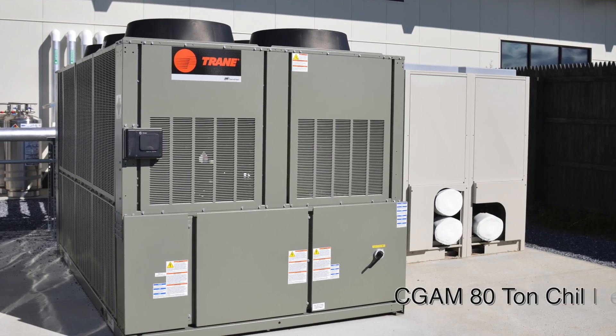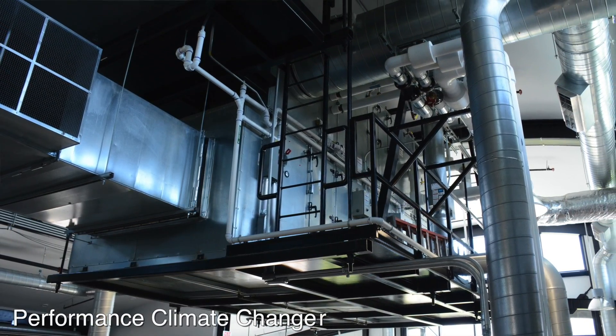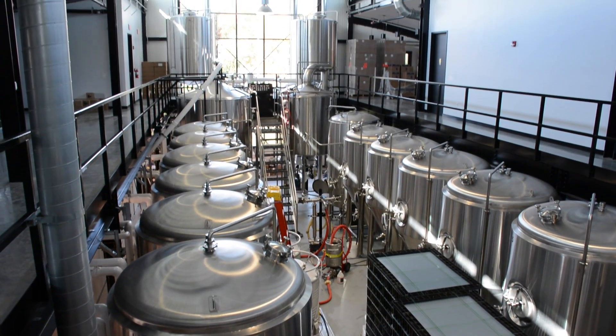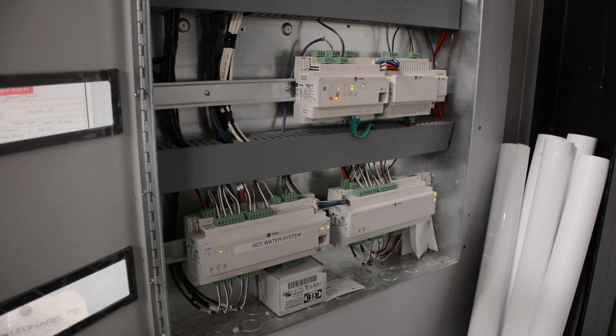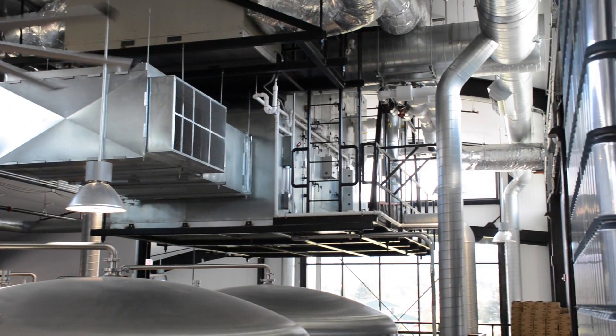For the chilled water system on this project, we chose a Trane C-GAM 80-ton chiller, and it has onboard pumps with VFDs. The main reason they chose to do it that way is that it limited the footprint inside the building and allowed the brewery to have more space for their own systems, limiting the mechanical space required. It also has factory-mounted controls, which limited the amount of conduit and electrical that had to go out to the chiller.